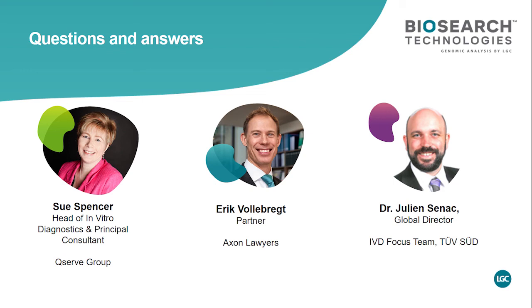Okay, so your performance evaluation data should be representative of what you're expecting to see on market. So it needs to be conducted on product that's been made in manufacturing conditions under SOPs. It doesn't mean it has to be full scale. If you made a smaller batch size, then as you scale up in the future, you need to validate that scale up to show that it continues to be representative. But that's the key driver here: the data you're producing has to be representative of the final product. So unfortunately, it does have to be on SOPs, and it should be in the manufacturing environment as well.